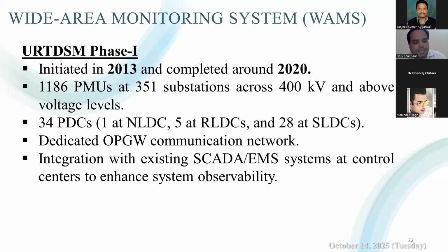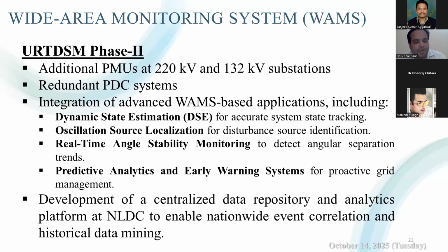So in short, we can say phase 1 established the nation's foundational WAMS backbone. Now this is about URTDSM phase 2. Phase 2 focuses on widening and deepening the wide area measurement system coverage, and it added additional PMUs at 220 kV as well as 132 kV substations to provide finer visibility.